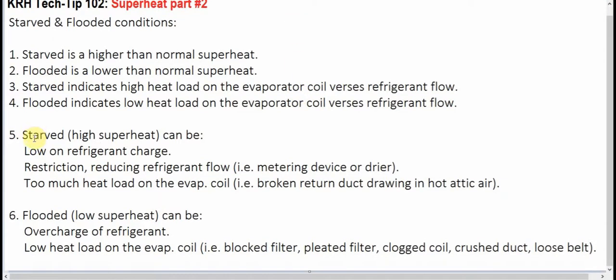So, a starved condition is a high superheat. Now, this can be a low refrigerant charge. Low on refrigerant, so we have less refrigerant going through our evaporator coil. This will cause a higher superheat. It could be a restriction, which is creating a reduction in refrigerant flow. This would be a restricted metering device or a restricted dryer.